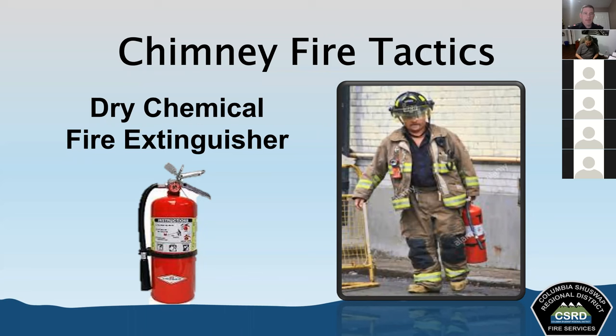The other thing to keep in mind is that dry chem fire extinguishers do not reduce heat in any way, right? You're just interrupting that chemical chain reaction. All the heat is still there, the fuel is still there, and the oxygen is still there. There's a much bigger chance of flare up if we're not reducing that heat, sucking the heat out of it as much as we can some other way. So just be aware of that. We're not looking at the hot fires that we're necessarily wanting to use this exclusively on. Anyways, we might also need to follow up with something that is going to reduce the temperature there.